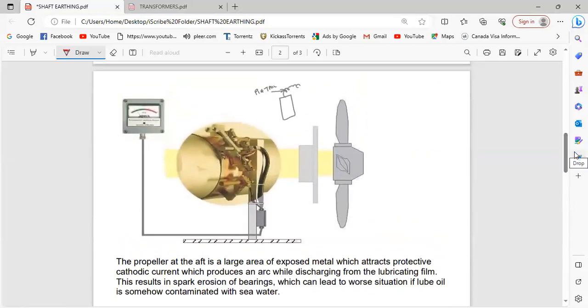Okay. So if this is dirty, which these two, remember this brush for your meter is totally different. It's got nothing to do with this. Okay, so what is happening if this has got dirty? That means your charges and all that are building up over here, no? And then they are discharging now due to the arcing over of that insulating medium, your lube oil flowing here. Now it is supposed to flow through this to earth. Okay, it is supposed to go like this to earth.